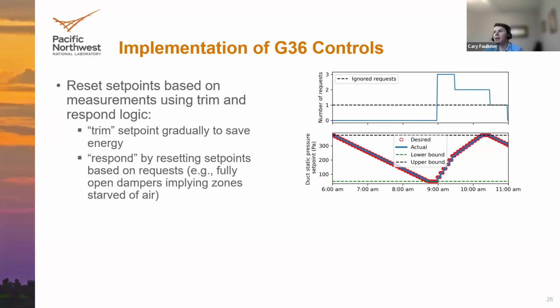So this plot on the right just shows a verification of our implementation of Guideline 36 using our models for the duct static pressure set point. I talked about how that's a key aspect of these VAV systems. So the top plot just shows the number of requests that we manually fed to the controller, but I'll talk about what those requests might mean. And then the bottom shows how the set point trims or responds based on those requests. So when there's 0 requests, then the set point gradually trims from a very high static pressure set point to a lower one. And there's some upper and lower bounds defined there just so you don't get crazy values.